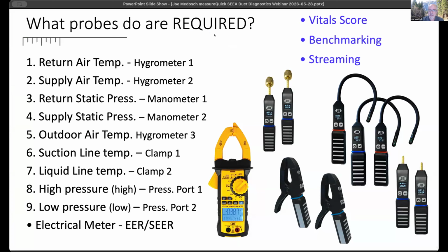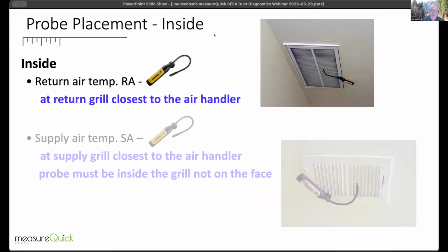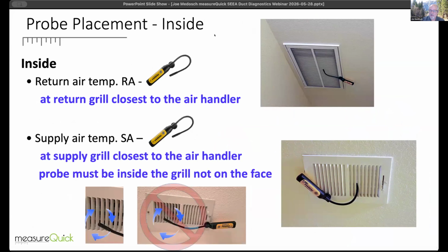So it's not a snapshot of measurements. These are all 9 probes on all the time, giving you live information, and they're completely dynamic, highlighting exactly what you need to know about this system while you're there and it's on. So here are the probes real quick. Inside, I've got one at the return and one at the supply. These are not in the unit. Notice that we're not measuring the appliance, we're measuring the system.